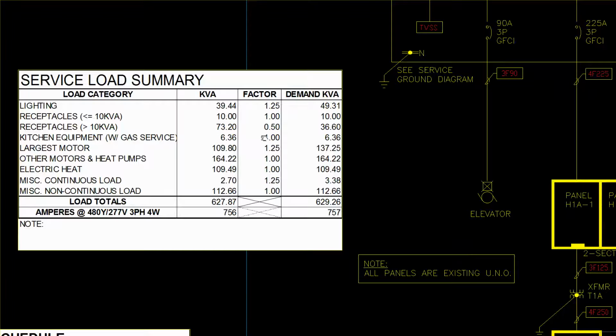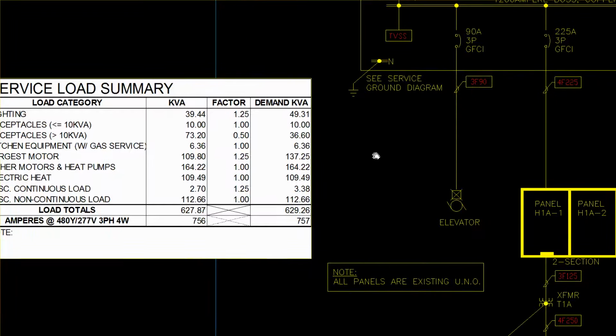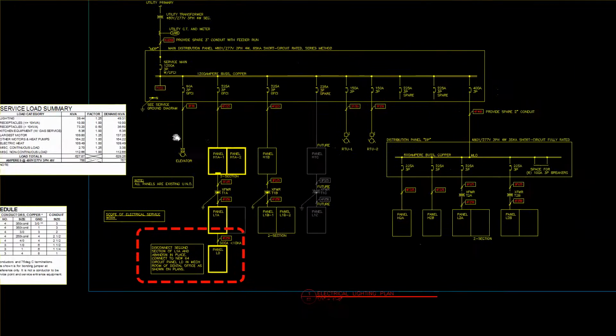Kitchen equipment. In our particular case, we didn't have a demand factor that was required, but in a big commercial kitchen, you can take different factors, sometimes as low as 0.55 or 0.65, because they know that in a big commercial kitchen there's diversity. That can help us have a more right-sized, realistically sized electrical service. So you see, just a couple of different one lines. There's 3 different one lines.